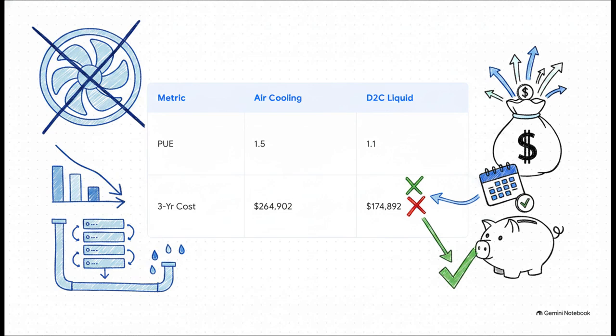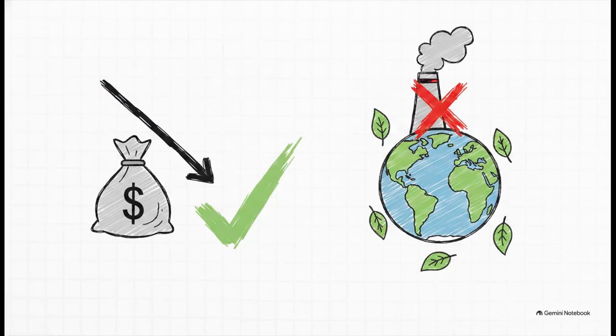Now I know what some of you might be wondering: installing liquid plumbing sounds expensive, right? Well, let's look at the financial reality. By removing those massive energy-hungry fans and reducing the burden on facility air conditioners, your power usage effectiveness, or PUE, drops from a bloated 1.5 to a hyper-efficient 1.1. In real dollars, even factoring in the estimated $30,000 upfront cost to implement liquid cooling, the energy savings are so massive that a single rack saves over $60,000 over just 3 years. It essentially pays for itself in less than a year, and then becomes a massive profit generator by slashing those operating expenses.